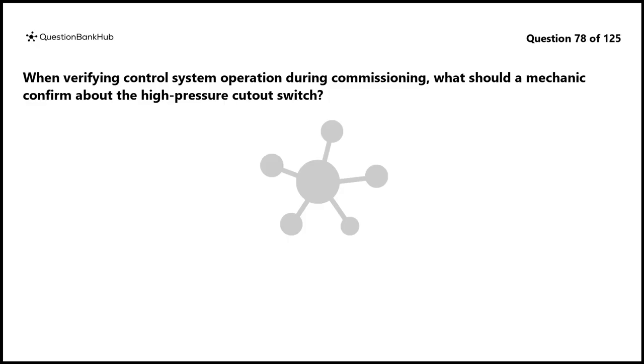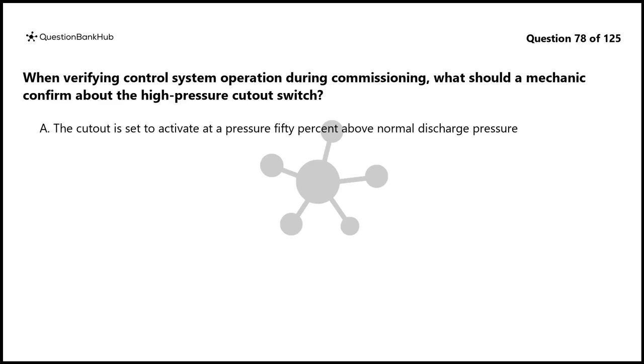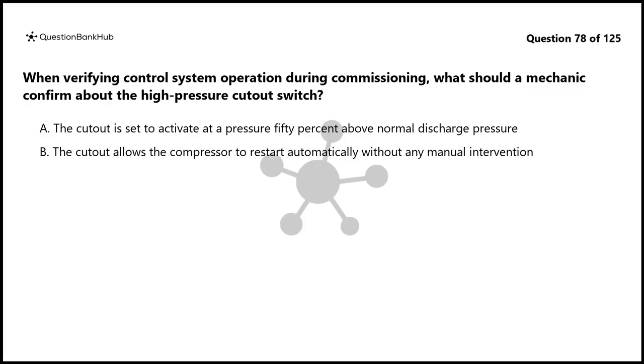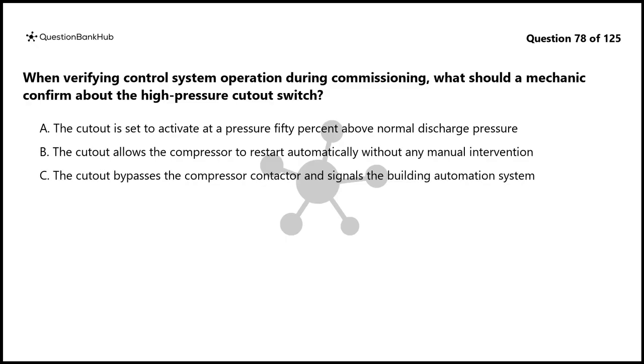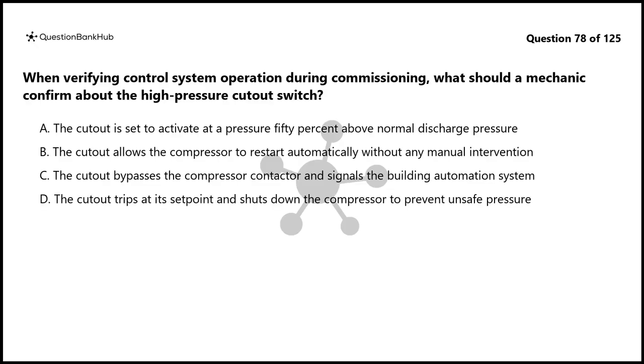Question 78. When verifying control system operation during commissioning, what should a mechanic confirm about the high-pressure cutout switch? A. The cutout is set to activate at a pressure 50% above normal discharge pressure. B. The cutout allows the compressor to restart automatically without any manual intervention. C. The cutout bypasses the compressor contactor and signals the building automation system. D. The cutout trips at its set point and shuts down the compressor to prevent unsafe pressure.